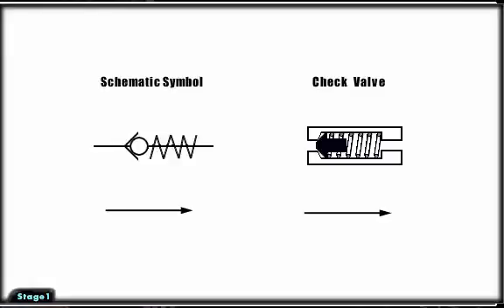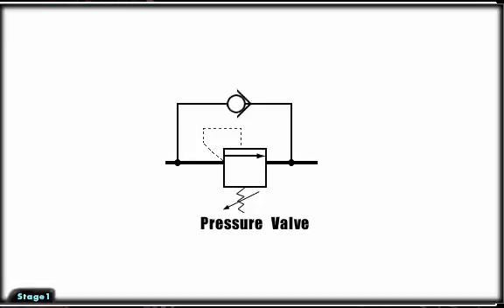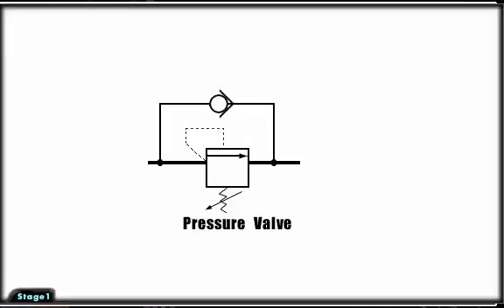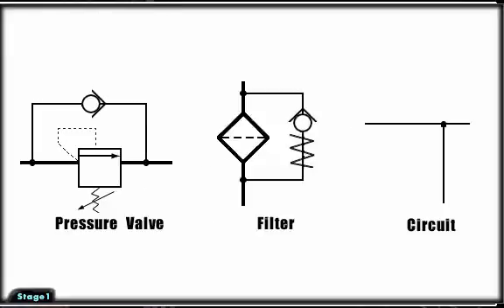The simplest check valve allows free flow in one direction and blocks flow from the opposite direction. This style of check valve is used when flow needs to bypass a pressure valve during return flow, as a bypass around a filter when a filter becomes clogged, or to keep flow from entering a portion of a circuit at an undesirable time.